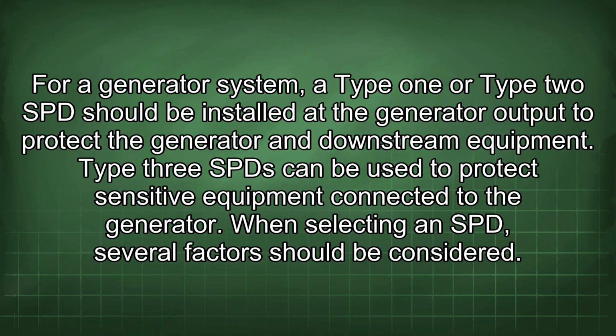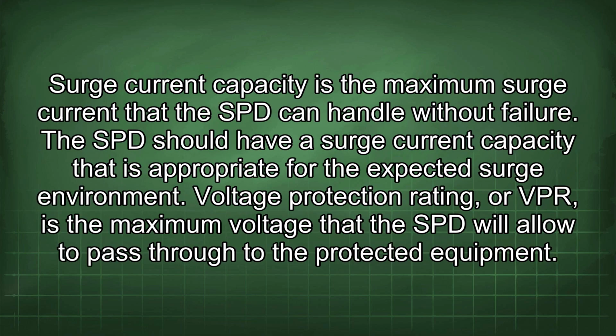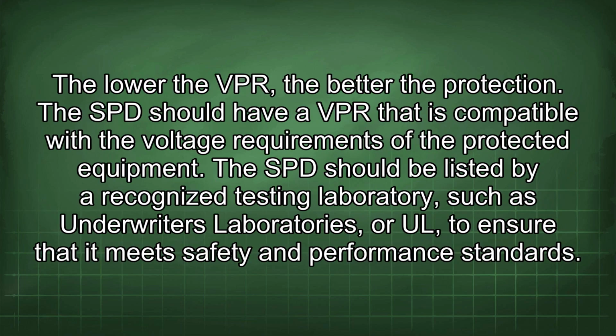When selecting an SPD, several factors should be considered. Surge current capacity is the maximum surge current that the SPD can handle without failure. The SPD should have a surge current capacity that is appropriate for the expected surge environment. Voltage protection rating, or VPR, is the maximum voltage that the SPD will allow to pass through to the protected equipment. The lower the VPR, the better the protection. The SPD should have a VPR that is compatible with the voltage requirements of the protected equipment.